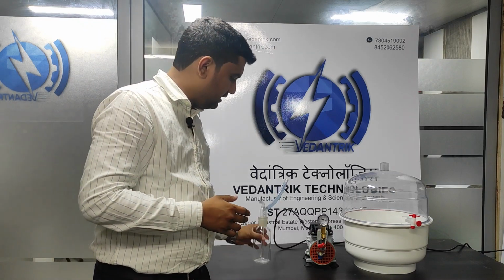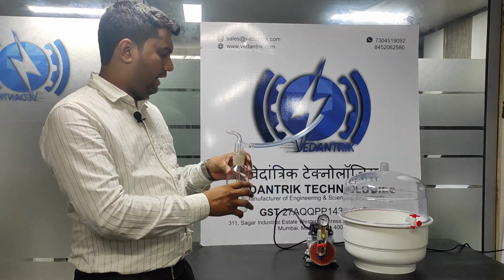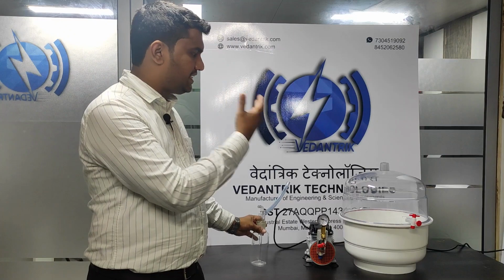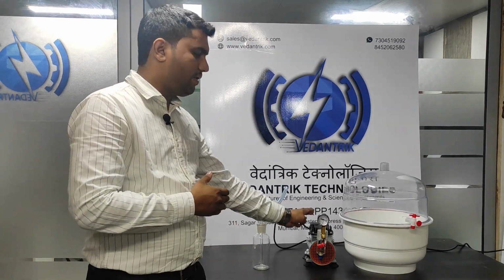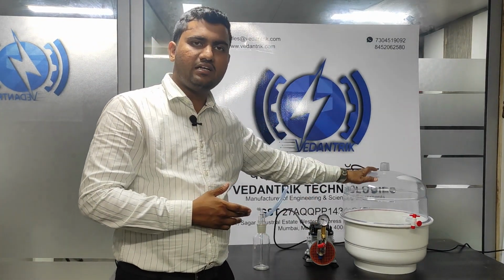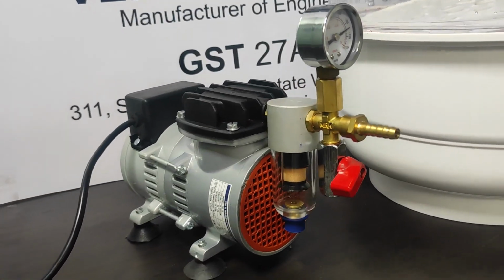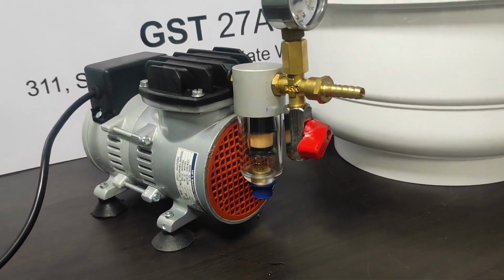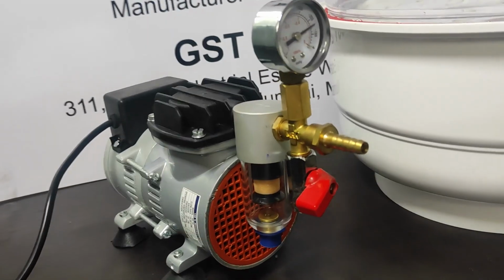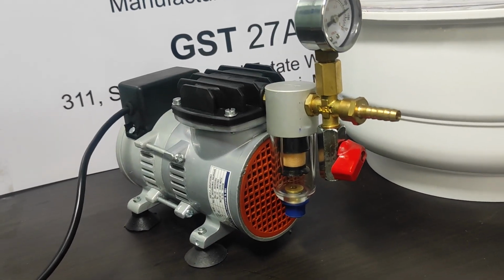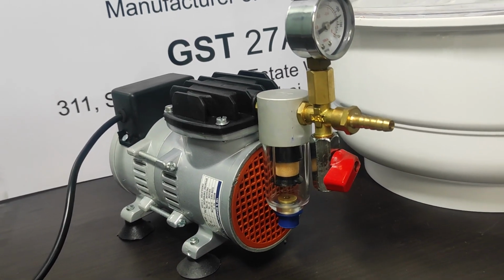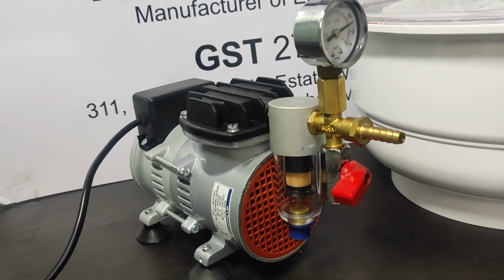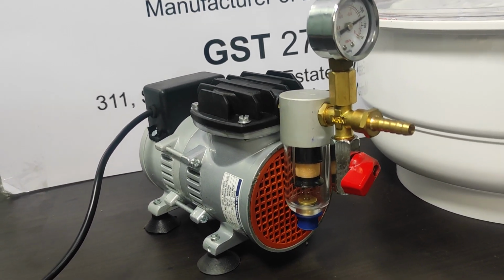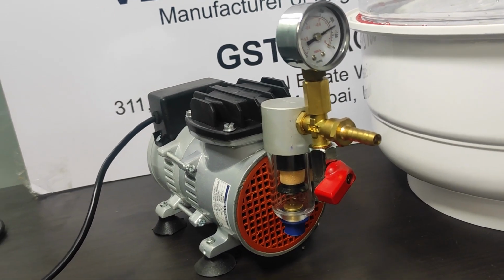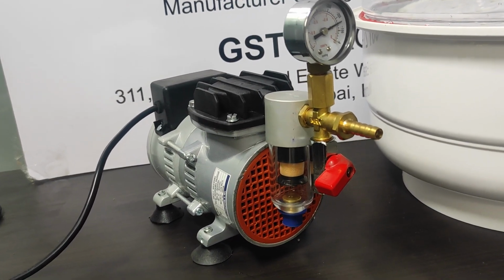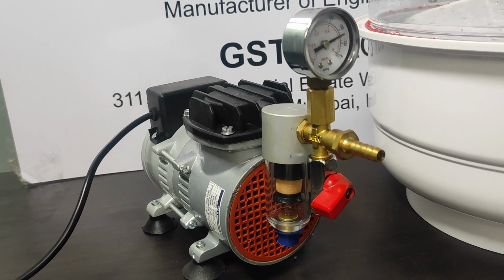You can see that this is a water trap, and it is installed between the desiccator and this vacuum pump. This is the vacuum pump and this is the desiccator. There are two types of pump. One is the oil type and the other is the without-oil type. This is the without-oil type of pump. It is a little costly and very easy to operate. In an oil type pump you are supposed to fill the oil from time to time. In this pump there is no need of filling oil from time to time. Also it will not create a problem of fumes.